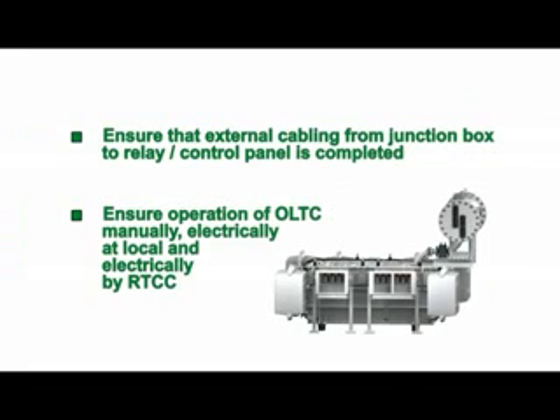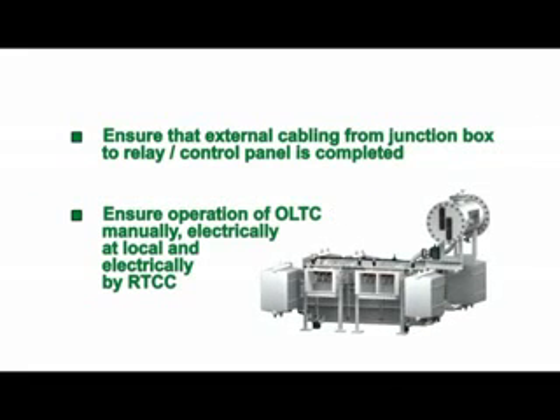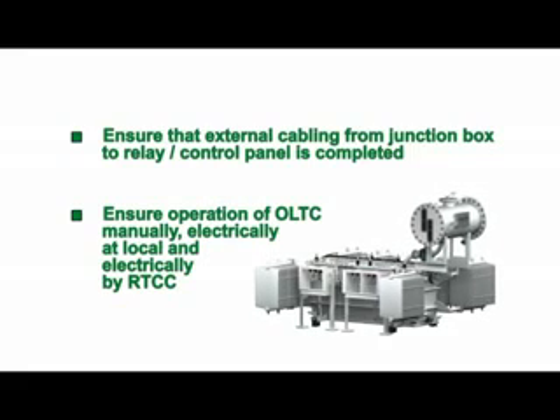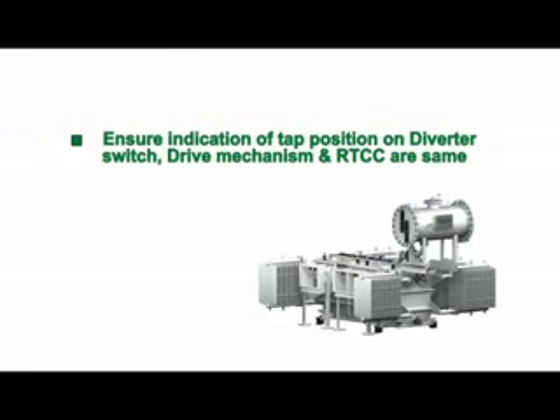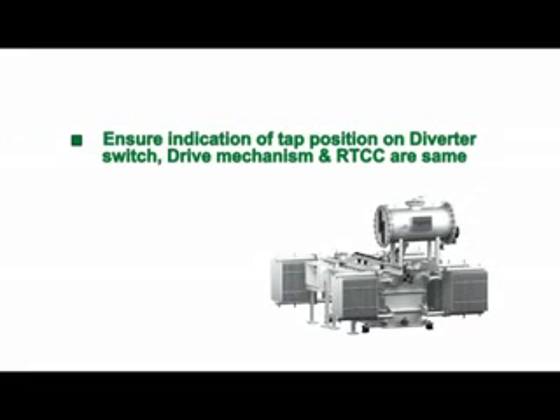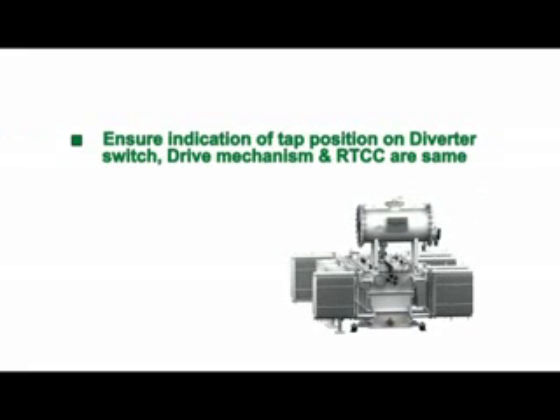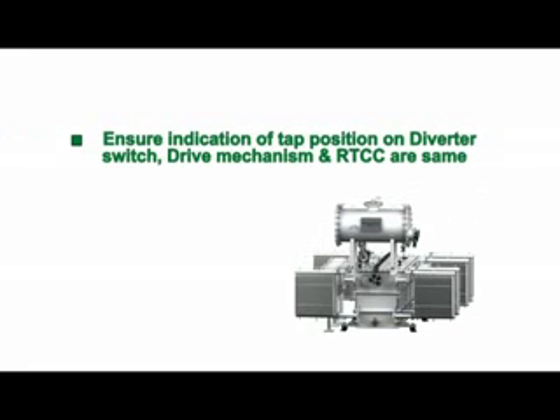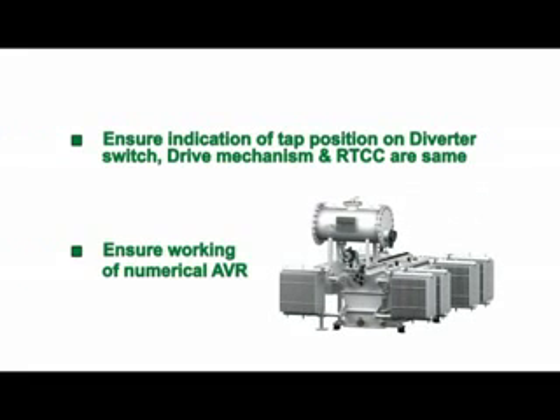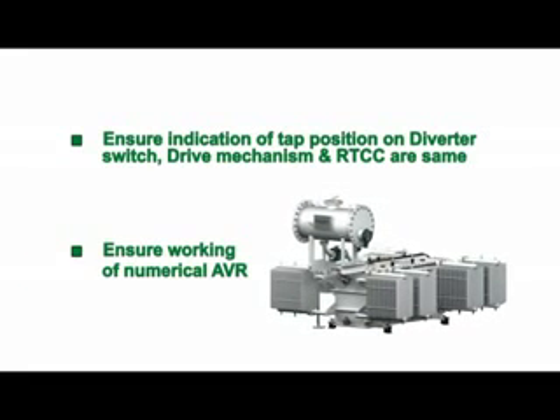Ensure operation of the OLTC manually, electrically and locally, and electrically by RTCC. Ensure indication of tap position on the diverter switch. Drive mechanism and RTCC are the same. Ensure working of the numerical AVR.